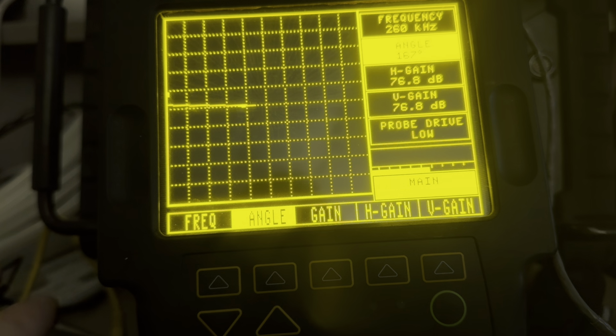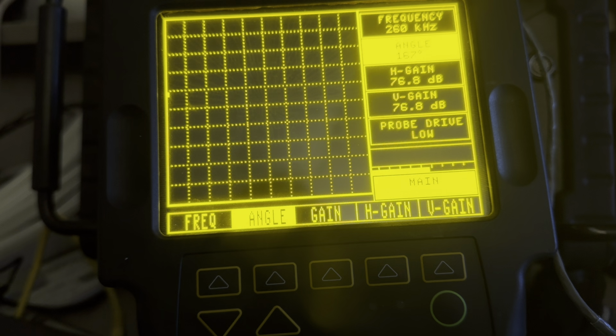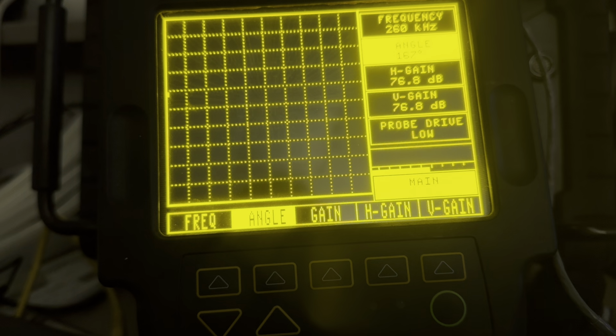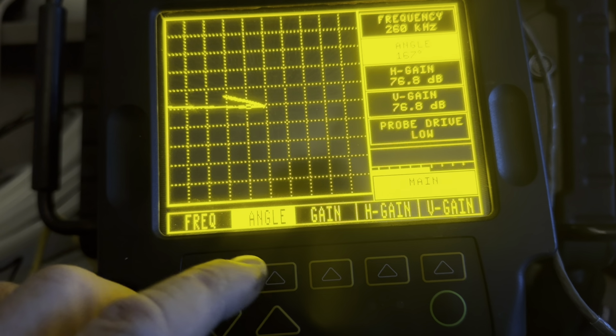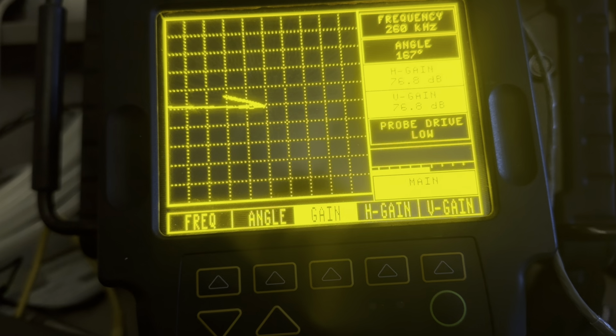But when I bring the probe down to the material, and I'll hit erase, and I'm decreasing liftoff, I'm slowly starting to load the coil with the EDM test block, and now you're on the operating point for this particular brand of aluminum. And now when I scan over one of the EDM notches, of course you can see the flaw. So I crank up my gain a little bit.